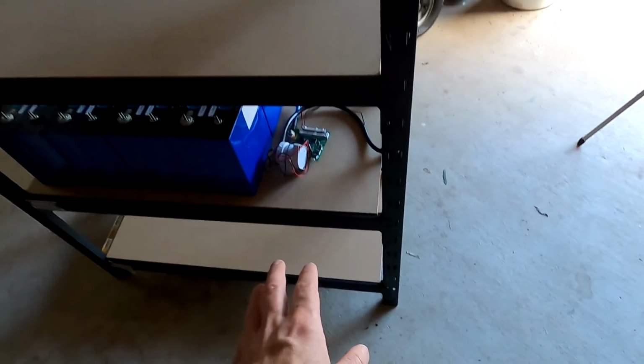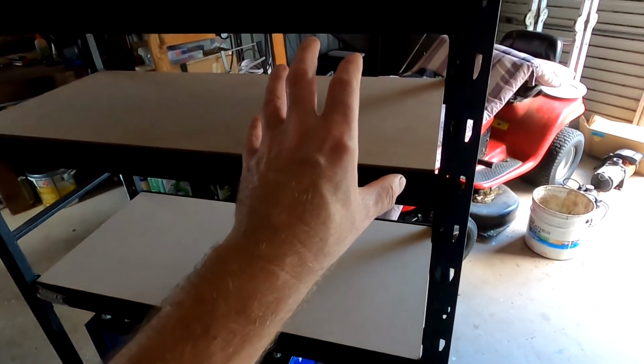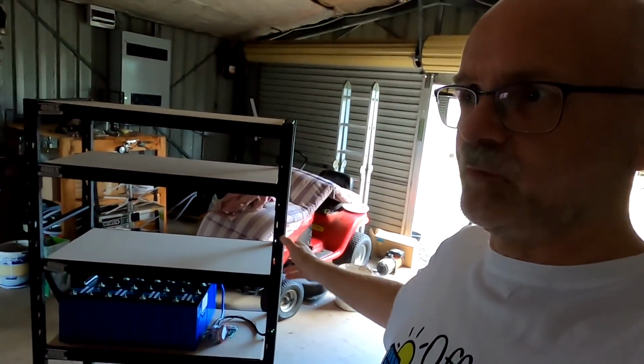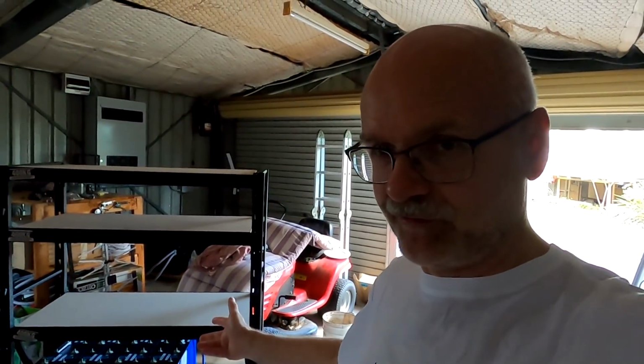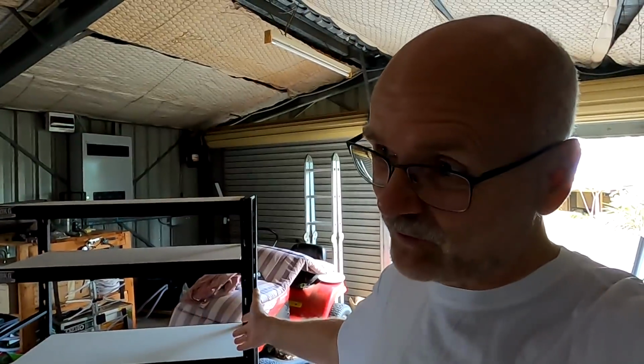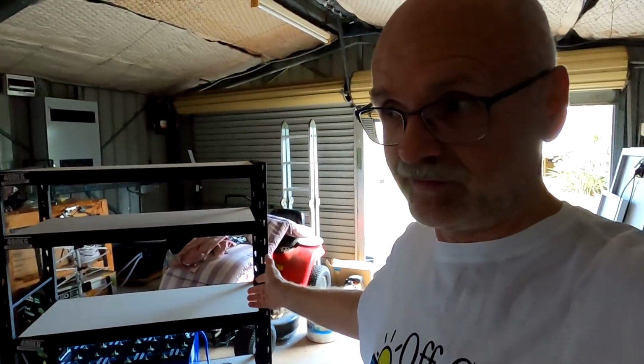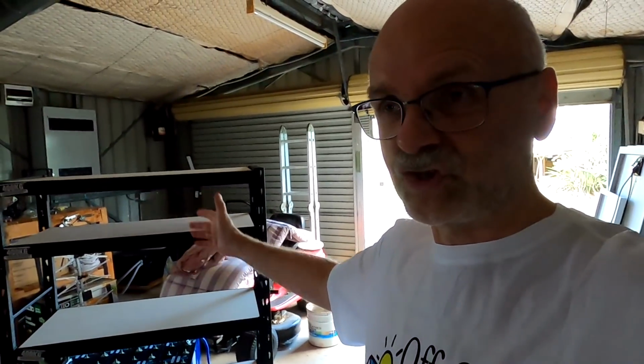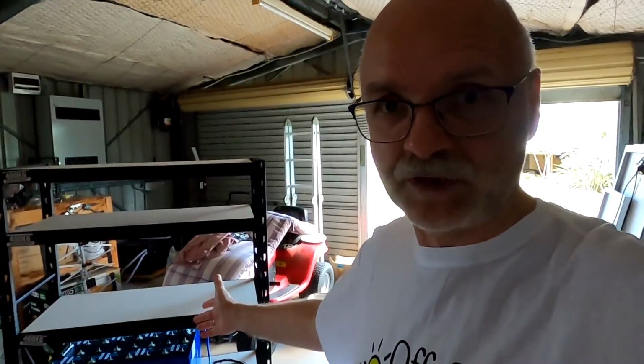Then there's the question, how do we connect all these battery banks together and to the main switch here in the upper compartment? At this stage I've got two possibilities. I can use cables - 35 mil, 25 mil would be all right for 80 amps. So I have to make sure they're all the same length, because otherwise we'll have different charge and discharge situations for each battery bank.